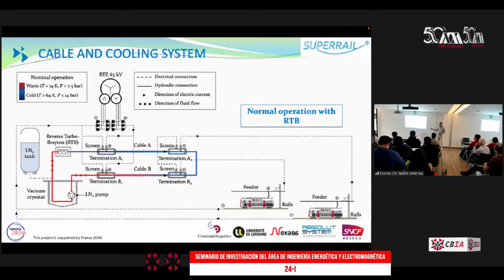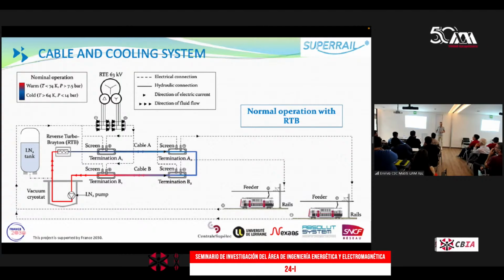So you start with cold liquid nitrogen here. The nitrogen warms up from the heat along the length of the cable. There is a need for a circulation pump, so you need a certain mass flow of liquid nitrogen to reach the required cooling performance. What drives the cooling system is essentially a kind of exchanger, here the reverse Turbo-Brayton. So you start with the nitrogen, it cools it down, and in a closed loop you have continuous circulation of liquid nitrogen, so there is no need to refill. You need at least one tank of liquid nitrogen at the start to fill the cable. And in case of an emergency, if you lose the liquid nitrogen for some reason, it's good to have some extra liquid available.